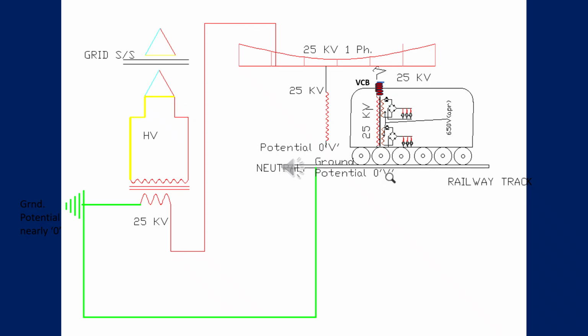It is also a stabilizing effect. If you keep one end at 0, the other end will be around 25 kV. It works to keep the voltage around 25 kV, but then it is going to the OHE. If you connect it with a load, then it will not be a short circuit. Suppose it is connected with the locomotive, then this circuit is complete through a load, and it will never be a short circuit. But if the OHE falls on the ground, there will be no load. Directly the OHE will touch the ground, and the circuit is completely without load, so it is a short circuit. But when there is OHE and there is no locomotive, then it will act as an open circuit. It will never be a short circuit.